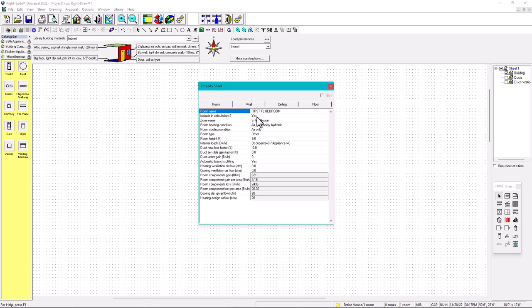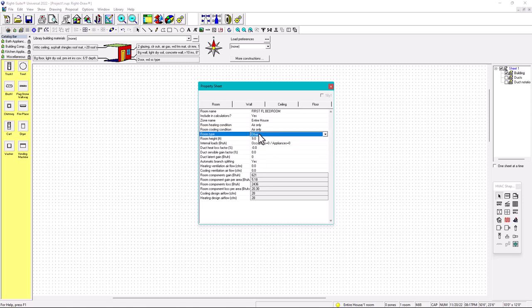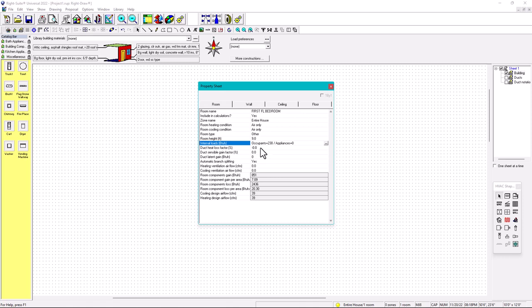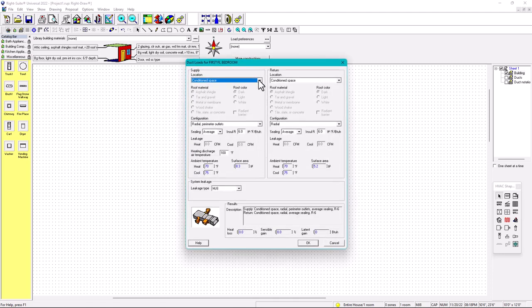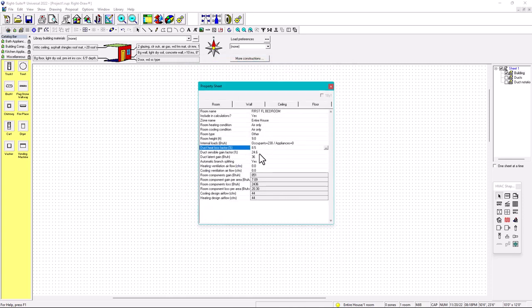We go to the first floor bedroom — room included in the calculations: yes. Zone name, room heating condition: we're going to put air only; room cooling condition: air only. Room type doesn't matter, you can leave it as Other. Room height could be nine feet or eight feet, whichever is appropriate for the project. For internal loads, for a first floor bedroom we're going to put one occupant. For the heat loss factor, since this bedroom is in a single home and my unit is in the attic, we're going to put vented attic.